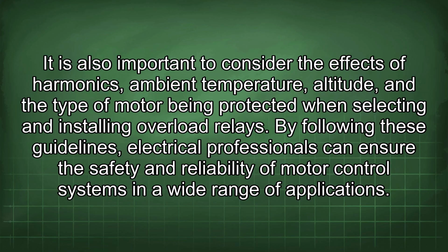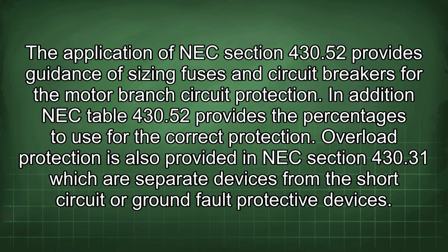The application of NEC Section 430.52 provides guidance of sizing fuses and circuit breakers for the motor branch circuit protection. In addition, NEC Table 430.52 provides the percentages to use for the correct protection.